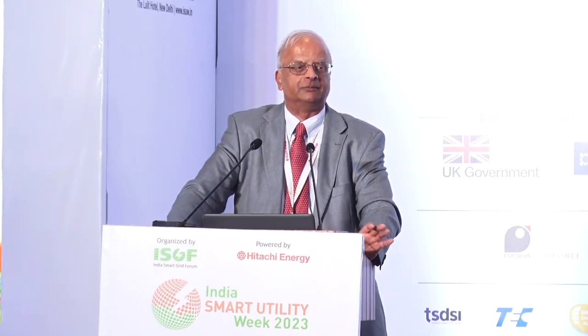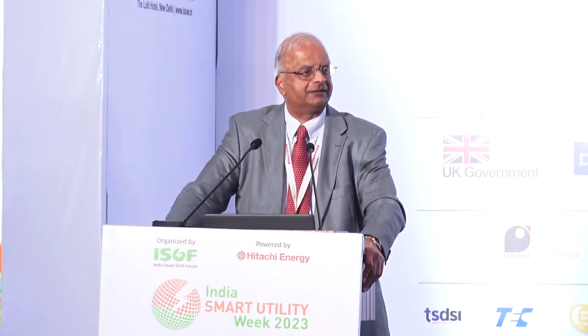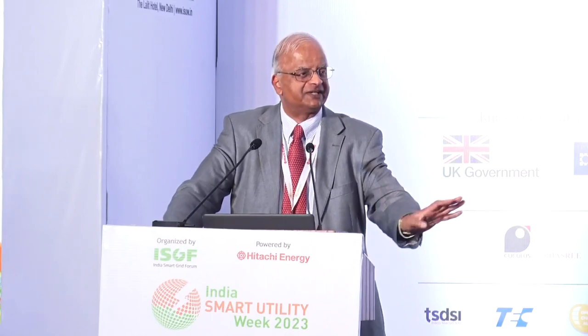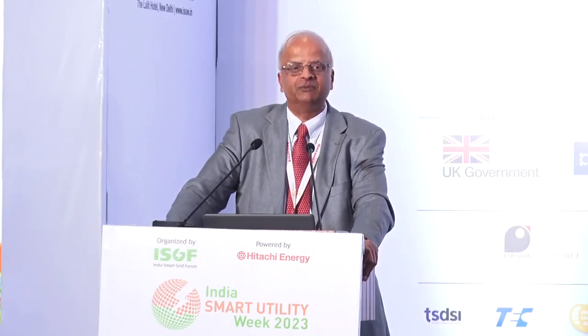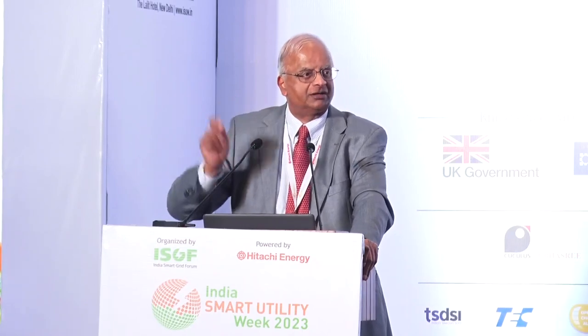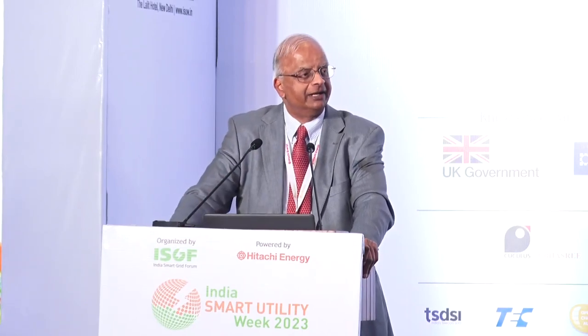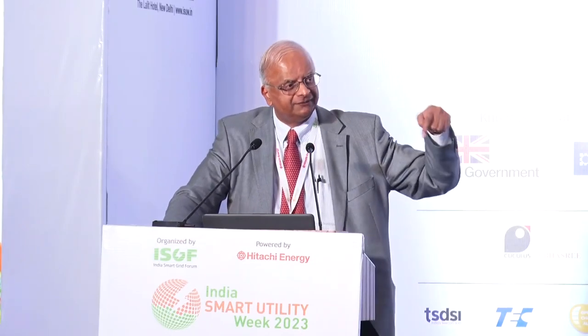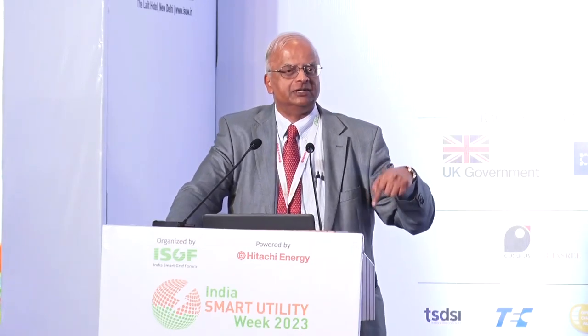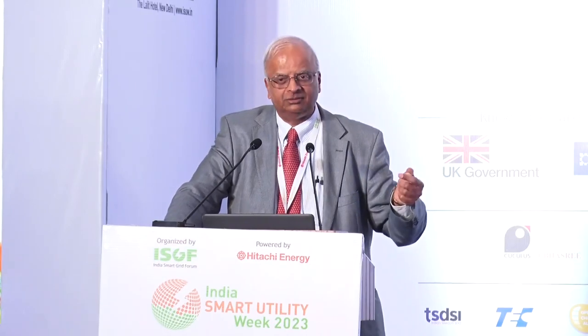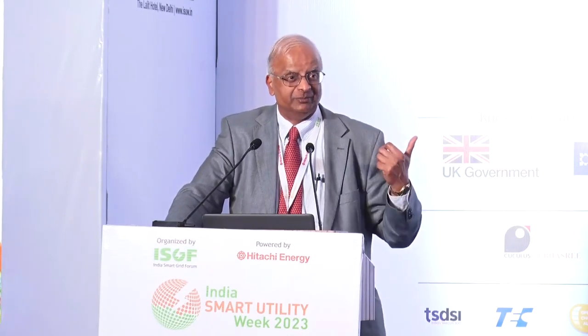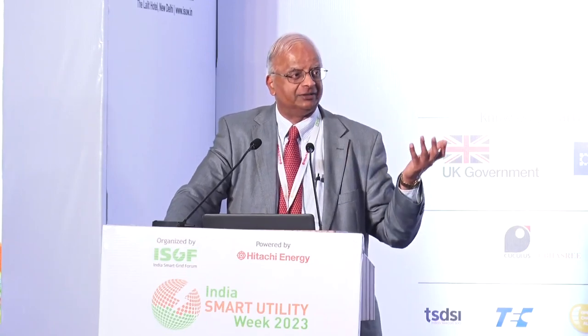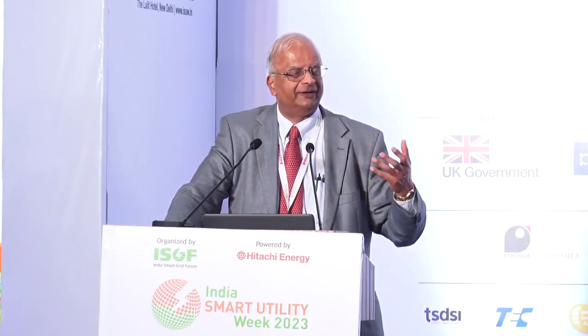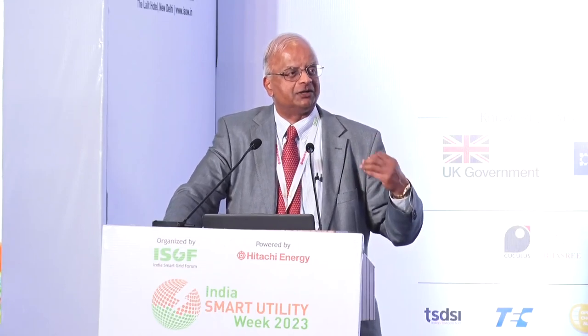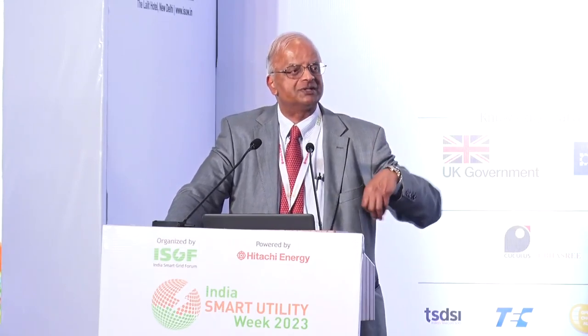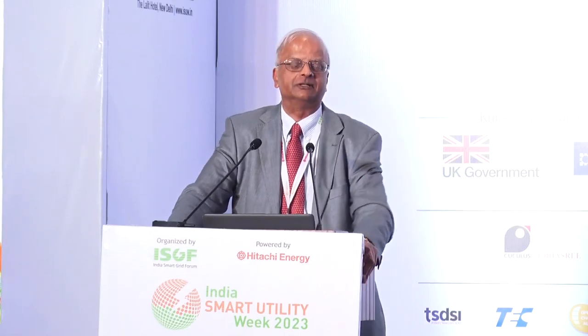About four or five years ago we put our minds together, and today we have a fiber optic temperature system that we've tested in seven experiments, and it seems to be working. We've wound the fiber on the coil of the transformer, and we're now able to get a 3D model every meter within the transformer winding to say, do we have hot spots we don't know about? Is the top oil temperature really the true measure, or was it just a convenient measure we've used all these years? We actually found that many other parts of the transformer, closer to the core steel, get hotter far quicker than the top oil temperature shows.